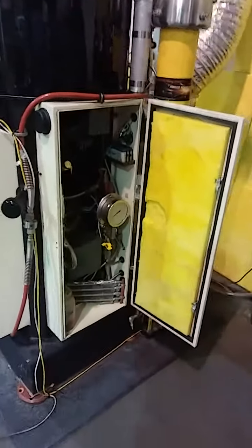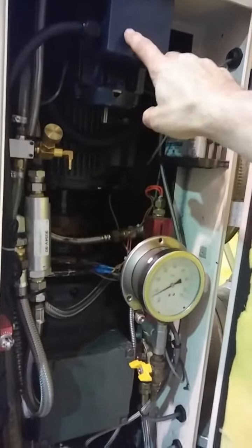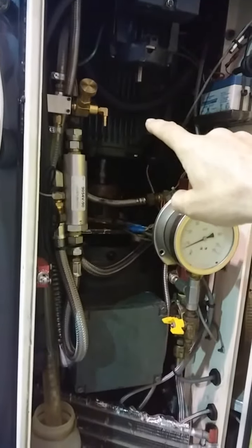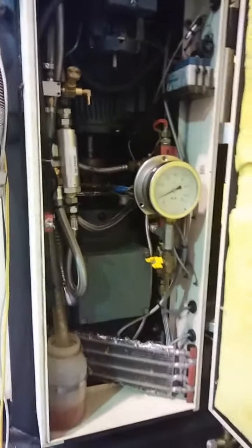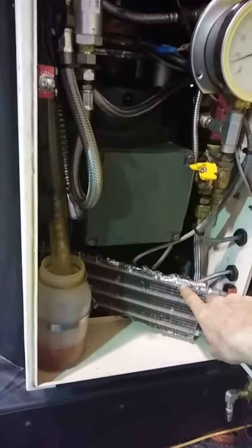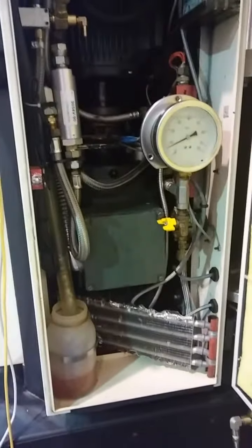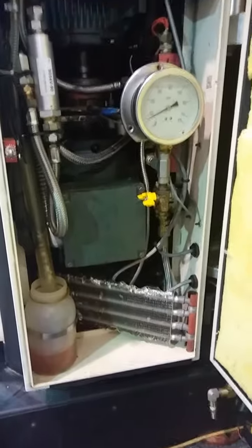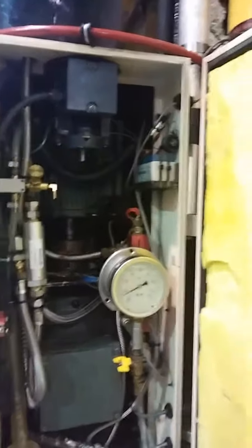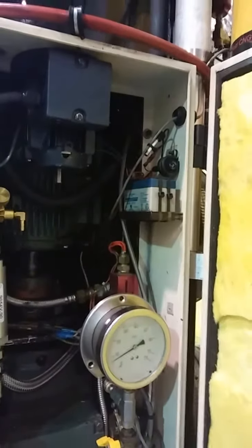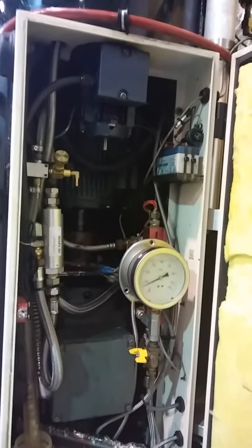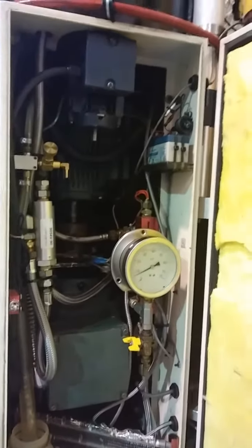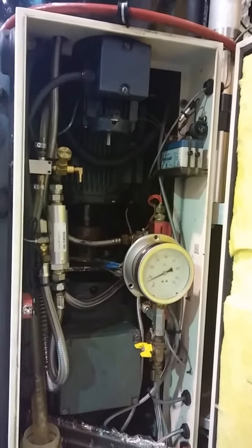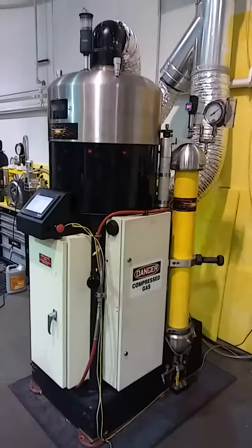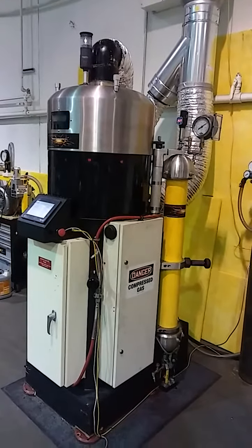Now we're at the other side, the other cabinet here, in which you can see this is the coolant pump, separate. One of the main drive motors and a larger main drive motor for direct drive to the compressor. This is the oil cooler. Again, high velocity fan. It's flushing with atmospheric gases and pushing that air on the oil cooler to help keep the oil cool. And this is a battery backup for the gas valve in case there's a power failure during an occurrence in which the valve needs to be closed. It's driven by that. If the battery gets weak or runs low, it runs through a self-test every time that battery is used. Okay, we're going to show you inside the main compressor unit.